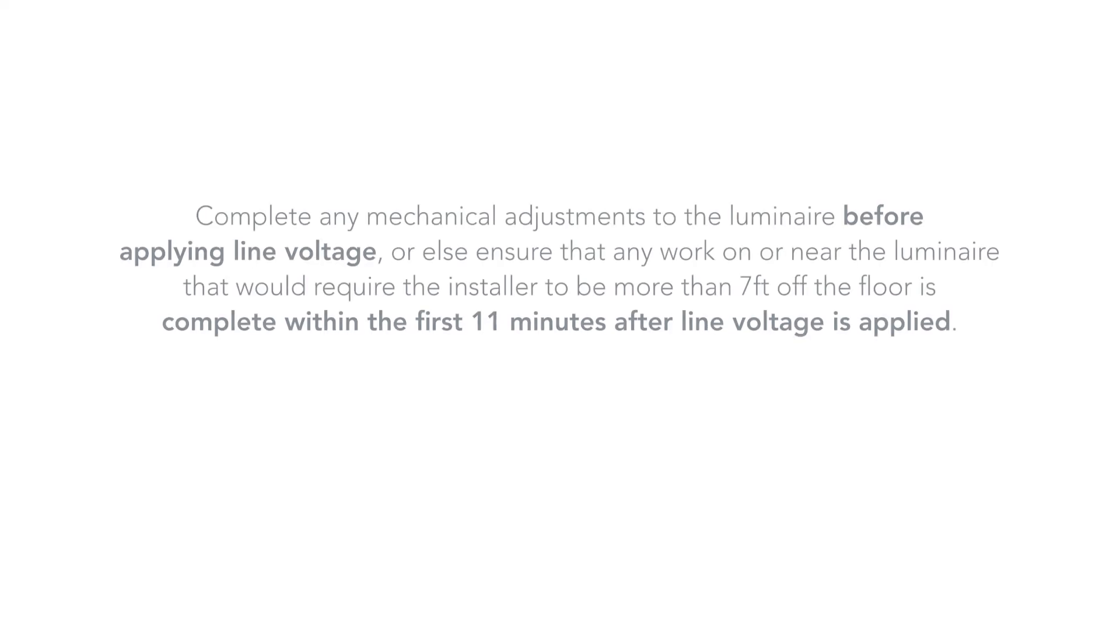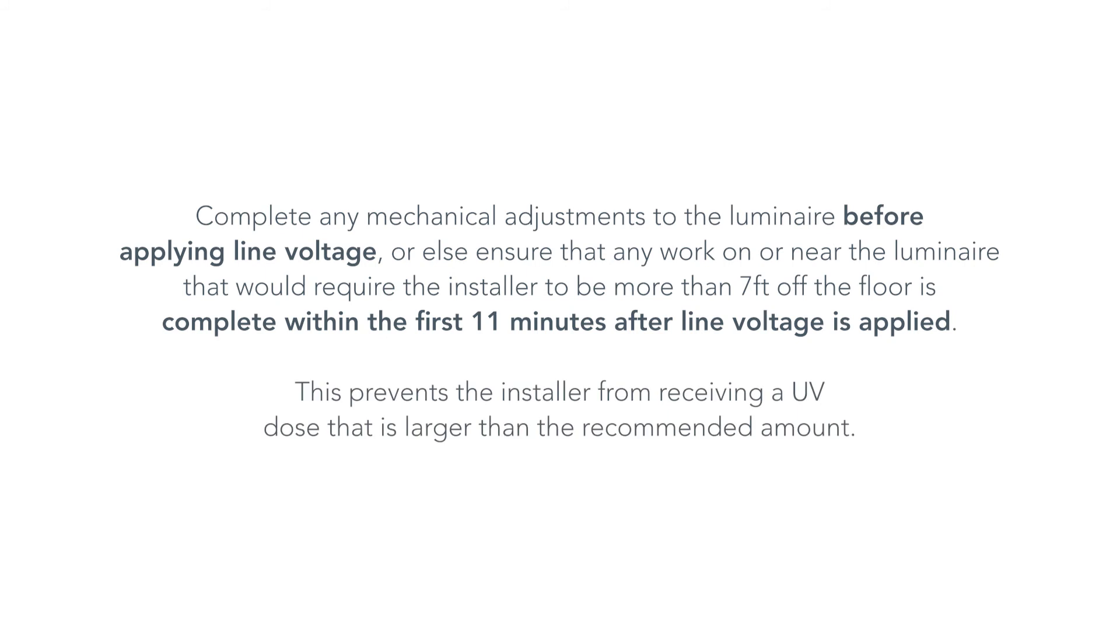Complete any mechanical adjustments to the luminaire before applying line voltage, or else ensure that any work on or near the luminaire that would require the installer to be more than 7 feet off the floor is complete within the first 11 minutes after line voltage is applied. This prevents the installer from receiving a UV dose that is larger than the recommended amount.